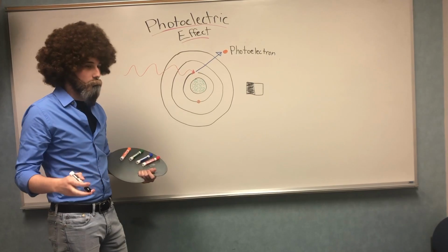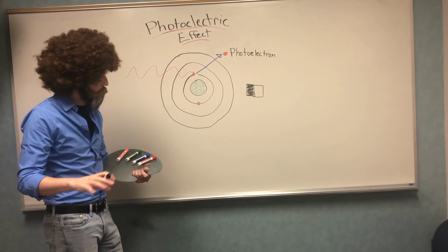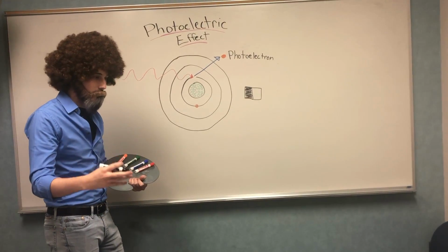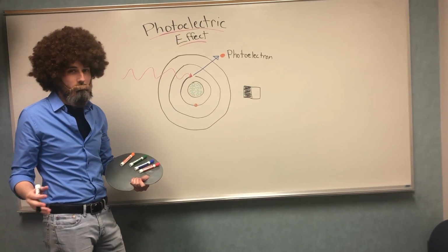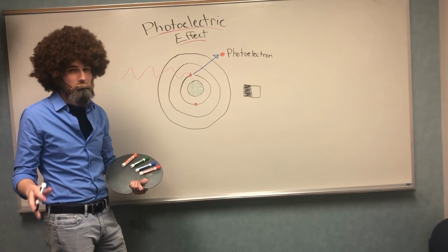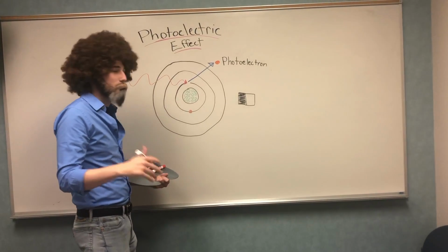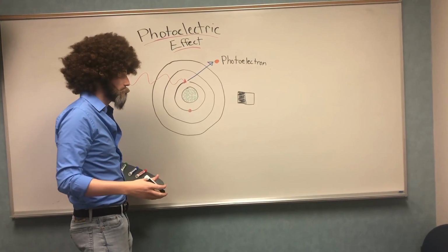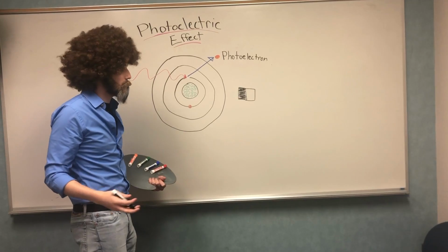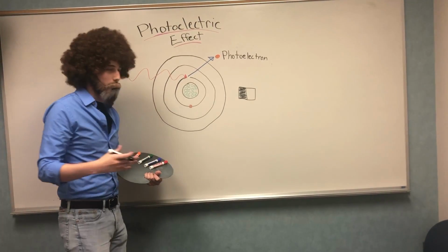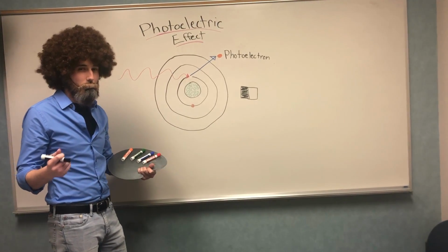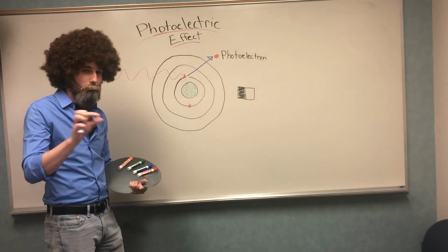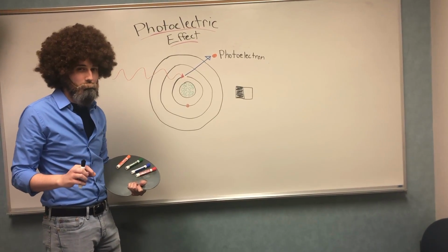Now, as the X-ray energy increases, less photoelectric effect, more penetration, then you're going to get a grayer look, a more dull look. We don't like that, it's a little sad around here. But it depends what you're looking at. If you're looking at an abdomen or something like that, maybe a few shades of gray is pretty good. But if you're looking at bone, you want a lot of that photoelectric to happen. So you go a little bit down on your kVp or something like that. You know, that sounds good.